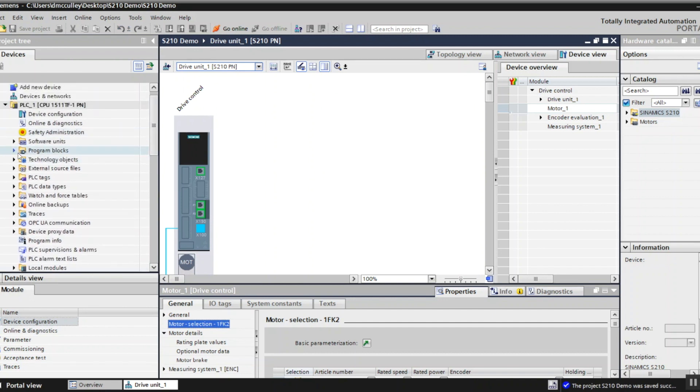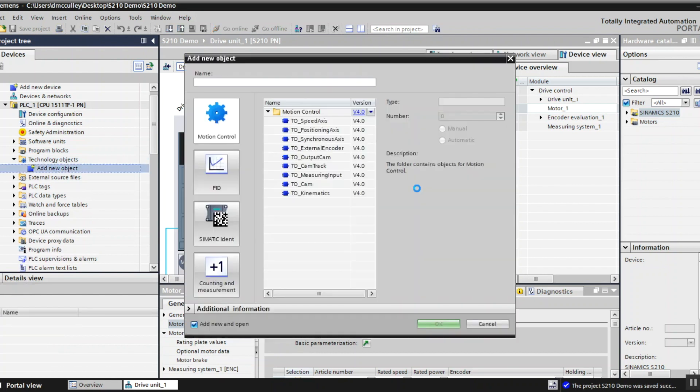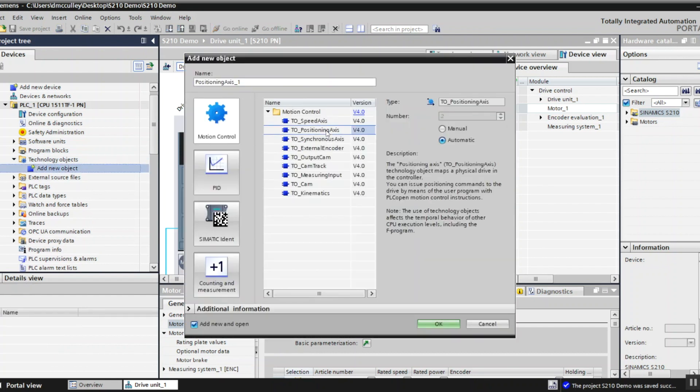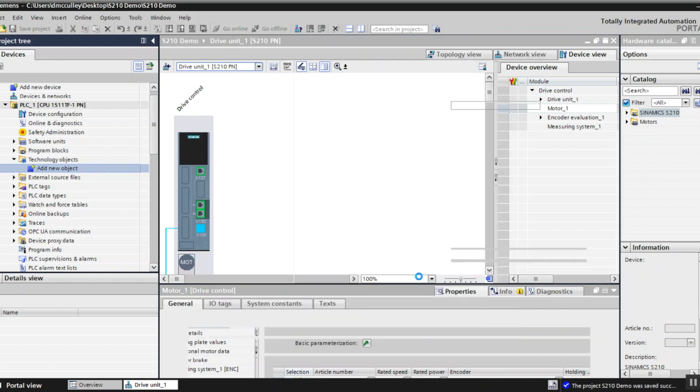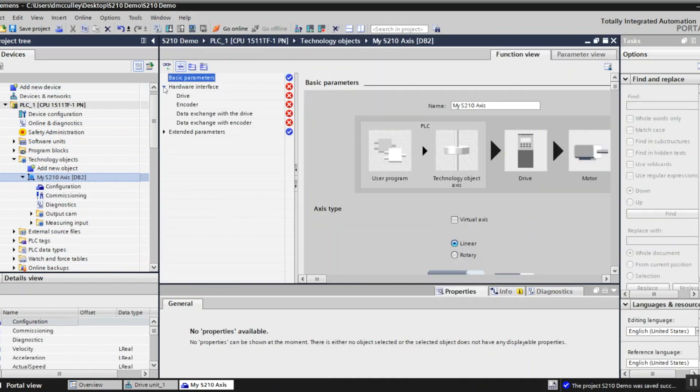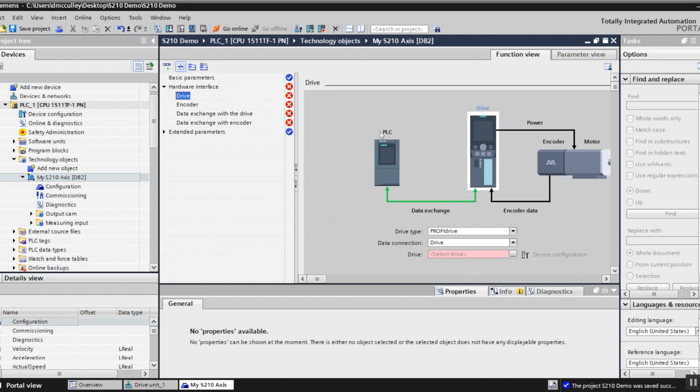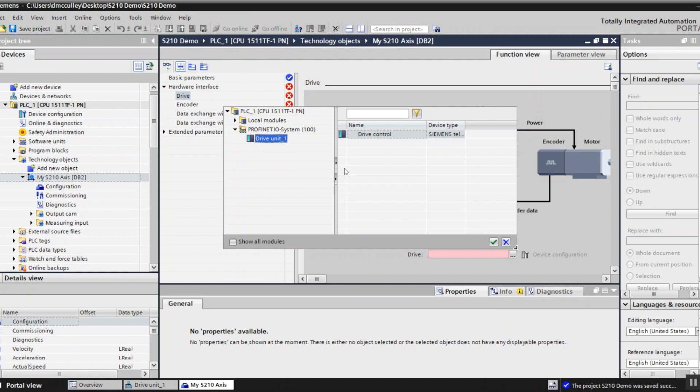Then I want to add the technology object to my PLC. I need a technology object to make it a positioning axis. I'll rename it my S210 axis. You can see a red X here so I need to assign which drive is connected to this technology object. Click here to drive, open this up, go to drive unit 1.